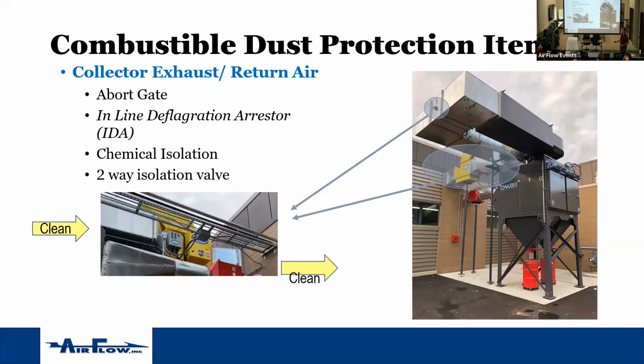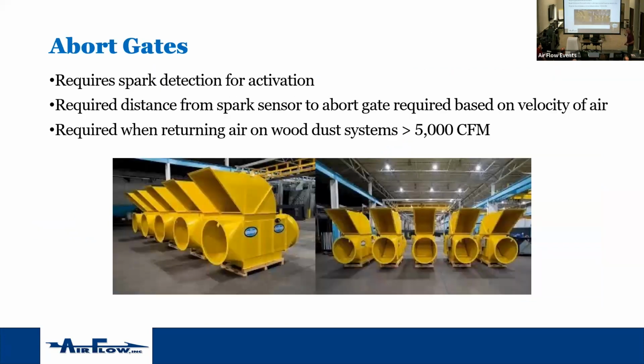So here's a picture of an abort gate. Your clean air will come into your abort gate. And it has a very large, heavy plate that's held up with magnets. Under normal operation, power's on the magnets, holds the device open, air is allowed to return to the space. When it activates, this is also controlled via spark sensor, but right next to the collector, there's also a distance, ironically, right? Spark sensor for when it actually sends a signal to the abort gate. There's a distance there that you have to be within to make sure that it gives that spark sensor enough time to make it through the control sequence back to the abort gate to shut down. Again, they do require spark detection for activation.